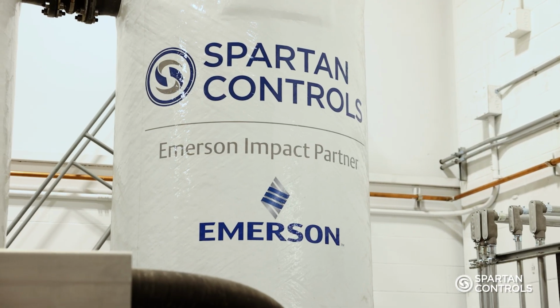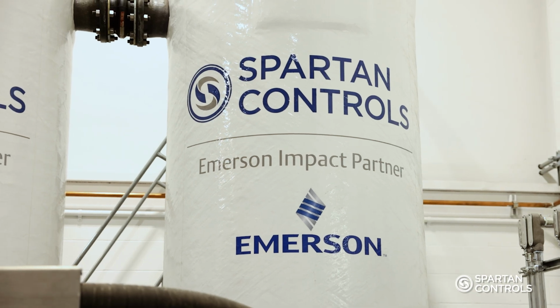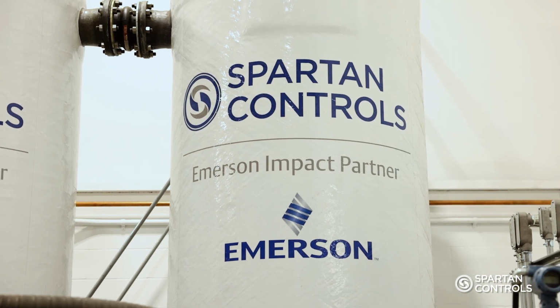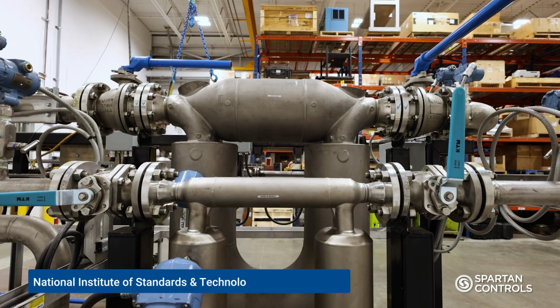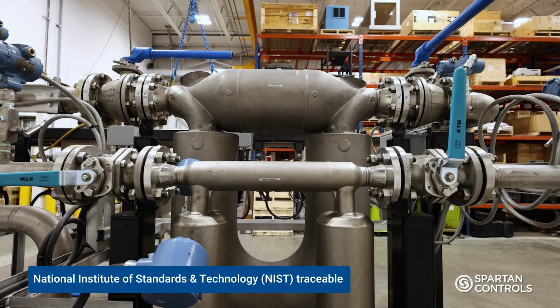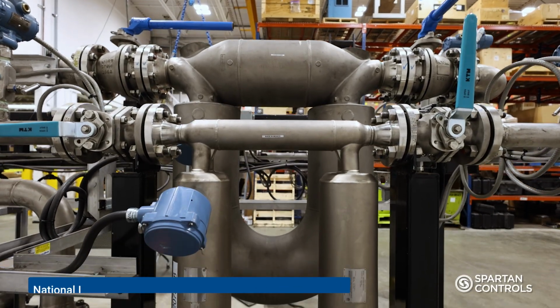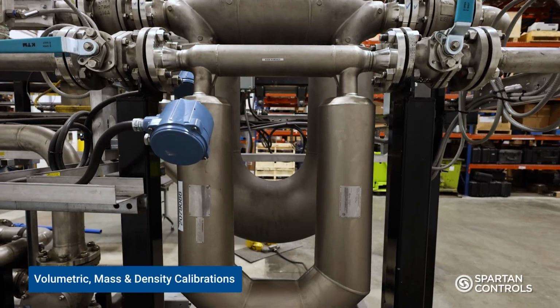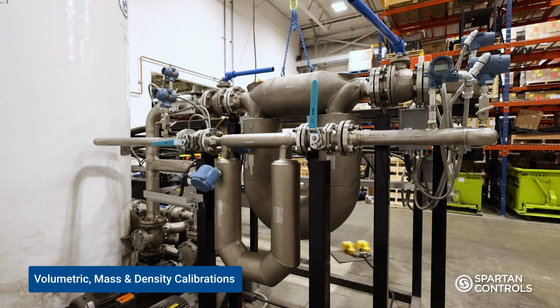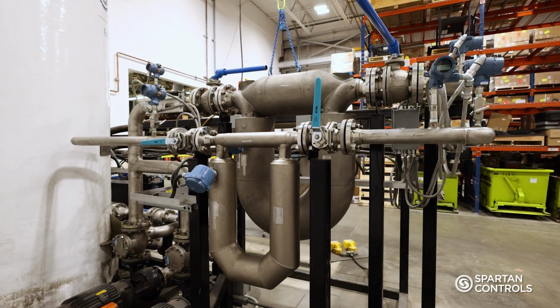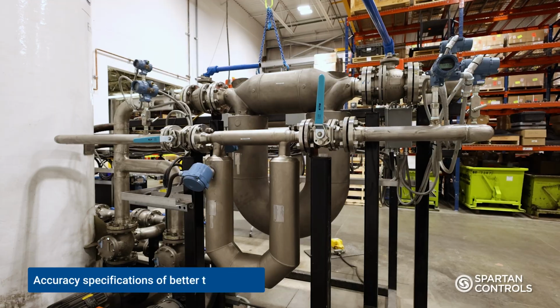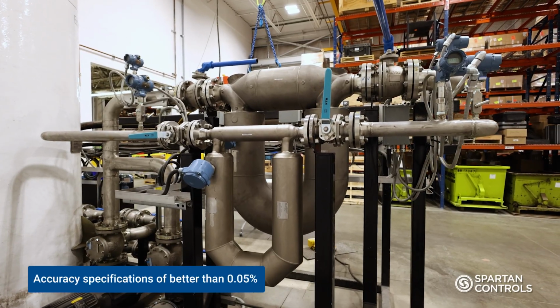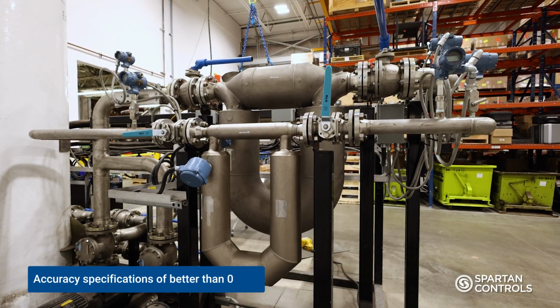In an effort to support our valued customers, we have invested in a master meter proving stand. This factory-certified, NIST traceable meter calibration stand provides volumetric, mass, and density calibrations on a wide range of meter technologies and sizes. The stand utilizes multiple Micro Motion master meters, calibrated to accuracy specifications of better than 0.05%.